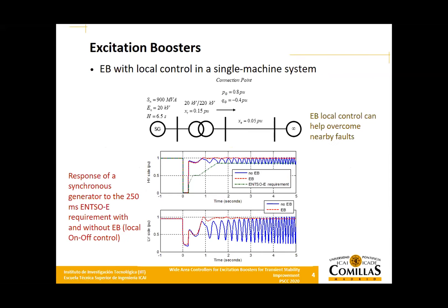We have here an application of the excitation booster in the case of a single machine infinite bus system, addressing the most demanding requirement of the ENTSO-E grid code. That code requires the machine to be stable in case of a 250 milliseconds fault. In blue, you have the system voltage response — the machine is unstable under this fault.